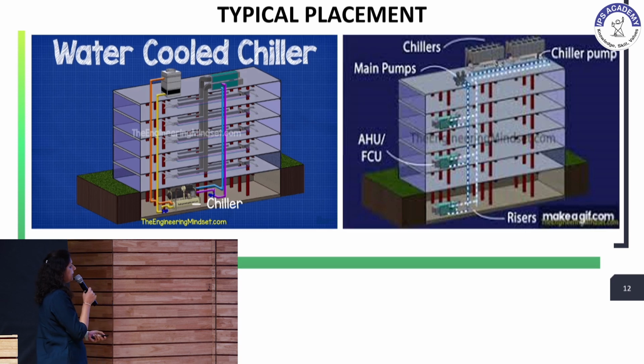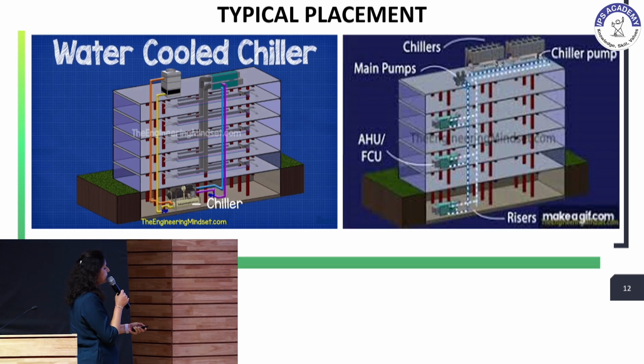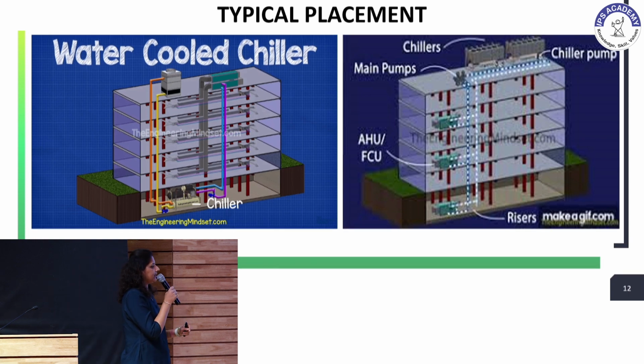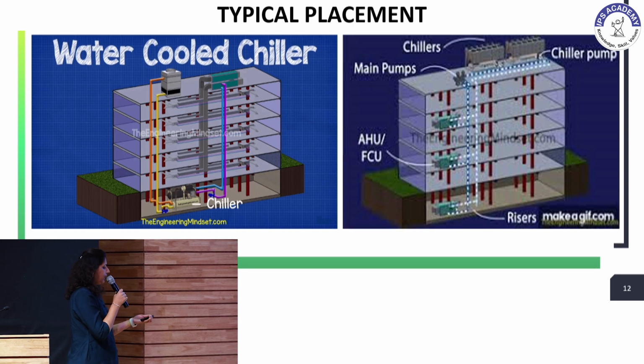This is a kind of installation which we do in water-cooled and air-cooled chillers. So water-cooled chillers are usually mounted in the plant room area with a set of pumps and a cooling tower which is mounted at the rooftop, which dissipates the heat to the environment. However, air-cooled chillers, when you see, they are mounted on the rooftop itself, and you just have the pumping systems and everything linked at the rooftop. So these are 2 types of installations which are different to each other.